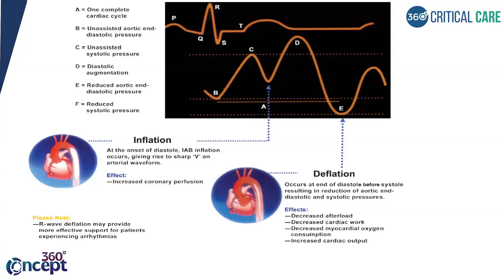Okay, we saw the timing, we saw the physiological effects. Now let us go into each parameter, how to set up a parameter on the console. So this is how your interface looks. We have something known as auto mode and semi-auto mode. Auto mode is for when you're not sure how to start, what trigger to select, and so on. You can just put it in auto mode. It will automatically select the appropriate ECG and start supporting. In semi-auto mode, you'll have to give some feedback or make some settings.